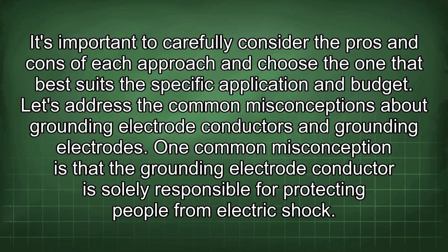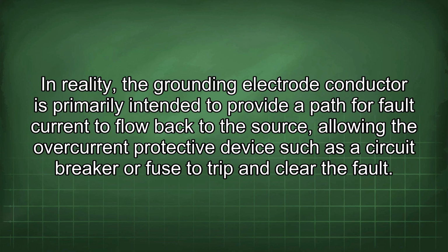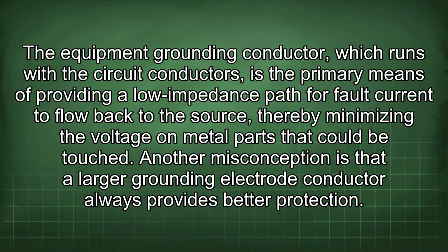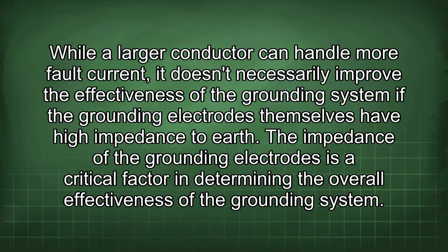One common misconception is that the grounding electrode conductor is solely responsible for protecting people from electric shock. In reality, the grounding electrode conductor is primarily intended to provide a path for fault current to flow back to the source, allowing the overcurrent protective device such as a circuit breaker or fuse to trip and clear the fault. The equipment grounding conductor, which runs with the circuit conductors, is the primary means of providing a low impedance path for fault current to flow back to the source, thereby minimizing the voltage on metal parts that could be touched. Another misconception is that a larger grounding electrode conductor always provides better protection. While a larger conductor can handle more fault current, it doesn't necessarily improve the effectiveness of the grounding system if the grounding electrodes themselves have high impedance to earth.